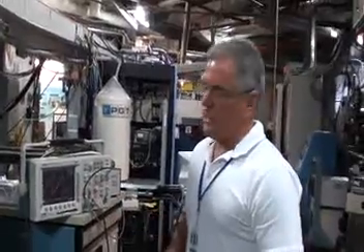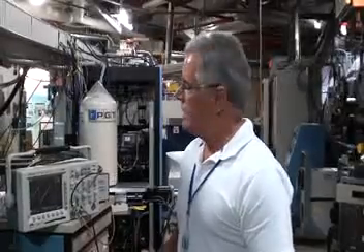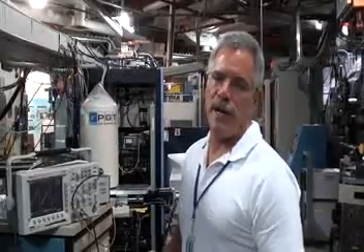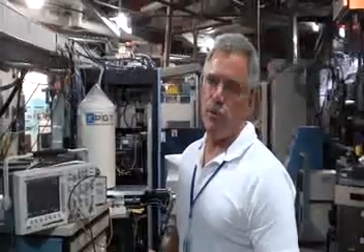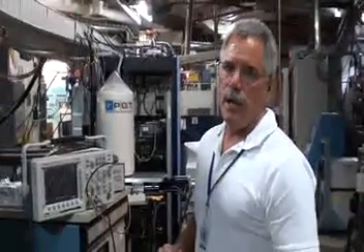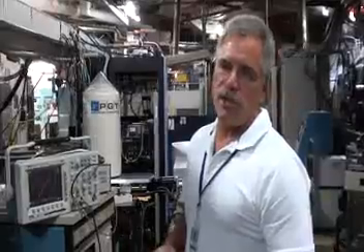Today, we're checking the reset rates on all seven channels on the multi-element array at Brookhaven National Labs. Reinstalled yesterday, it's been sitting overnight. The first thing we want to do is make sure that all the resets have settled down. The bias supply and high voltage have been on all night long. So far, we've looked at channel 1, and channel 1 is at 250 milliseconds. We'll be moving on to channel 2 now.